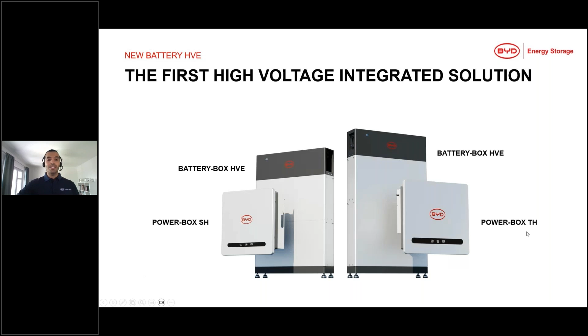The inverters, both single phase and three phase, come in different power classes. The single phase starts at 3 kilowatt and goes up to 6, and the three phase starts at 5 kilowatt and can go up to 15 kilowatt. It's possible to have up to 3 of those inverters connected in parallel in one system, each with their own battery, giving you the possibility to have up to 45 kilowatt of power with capacity of up to over 200 kilowatt hours if you have a battery connected to every one of the 3 inverters.